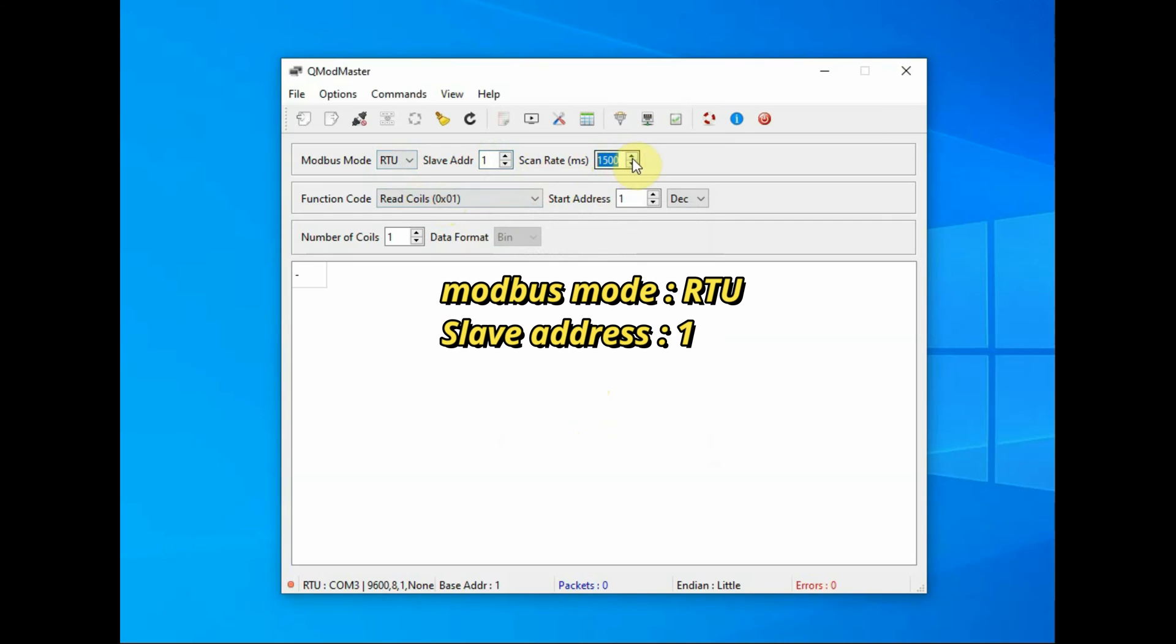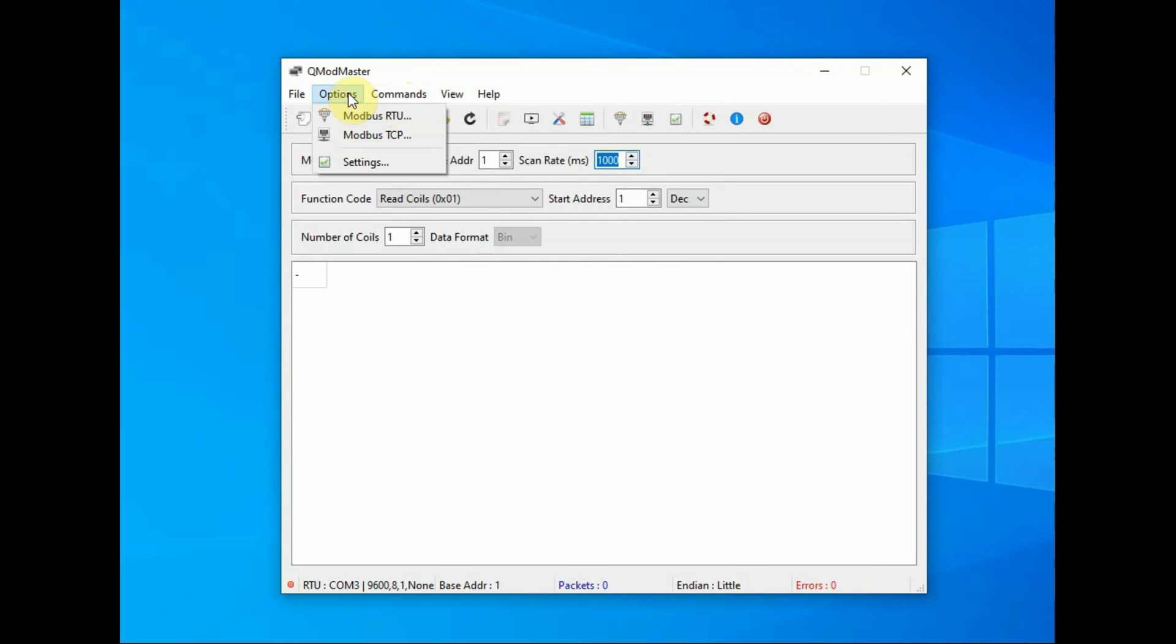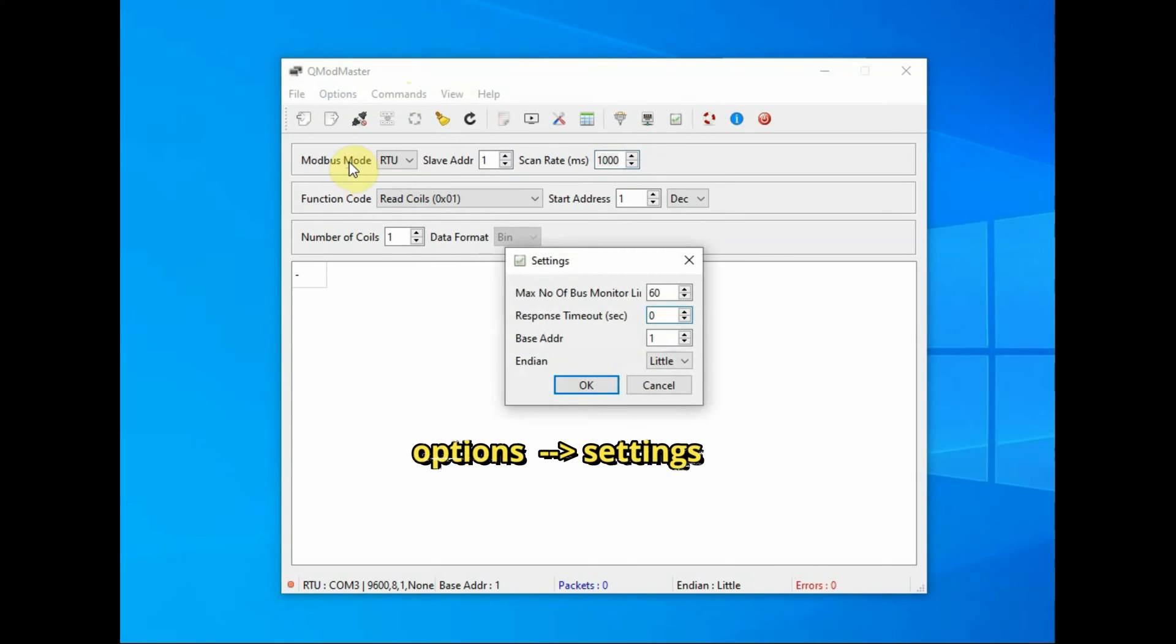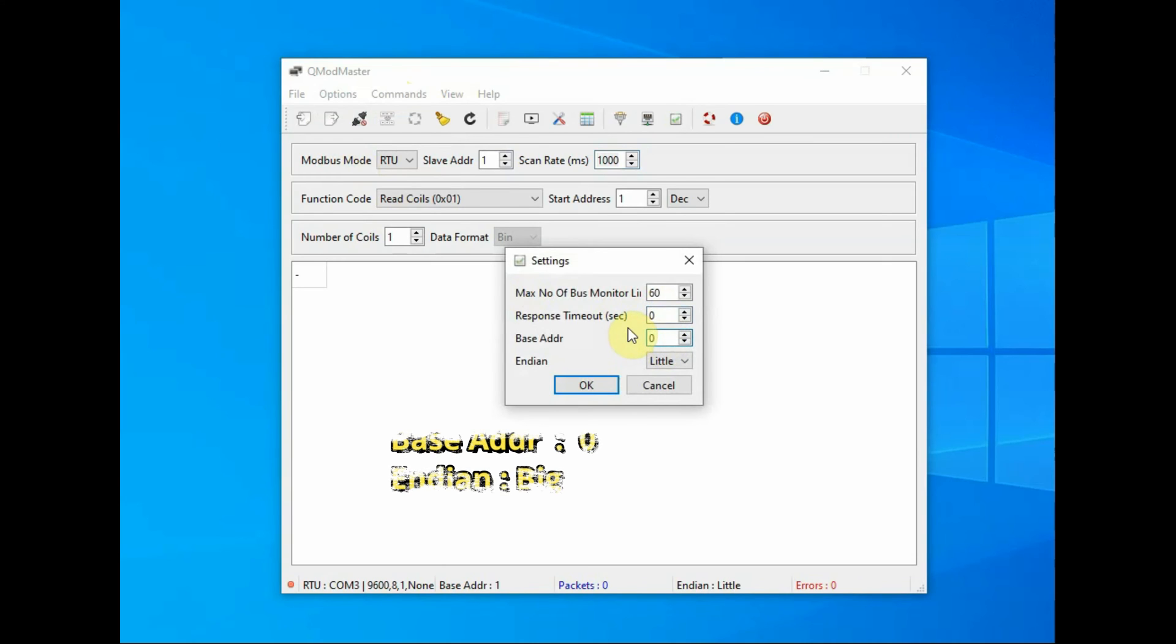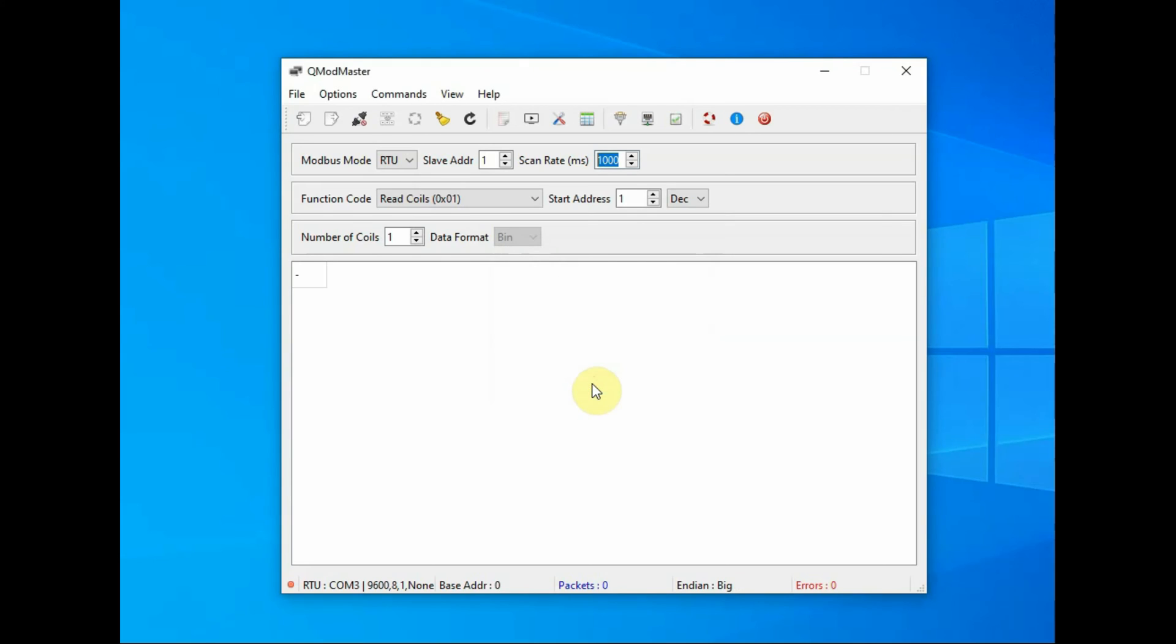Slave address is 1 and the scan time is 1000 milliseconds. From options settings, select the base address as 0, this is very important, and then select big-endian and then click on OK.